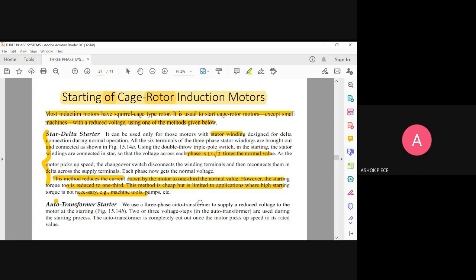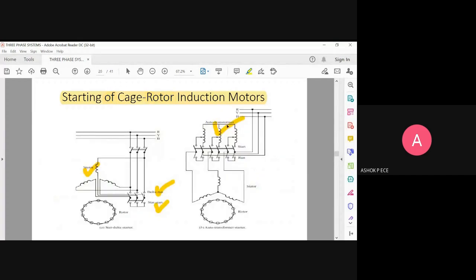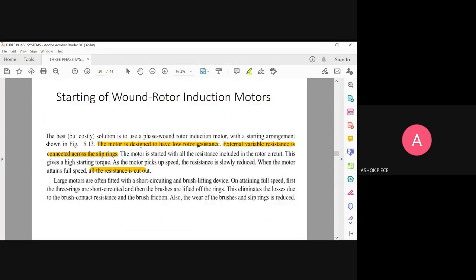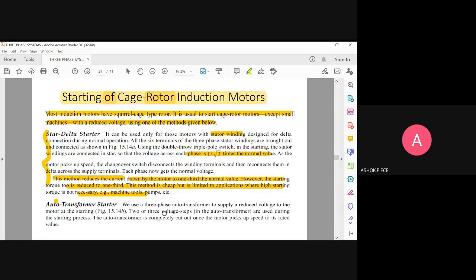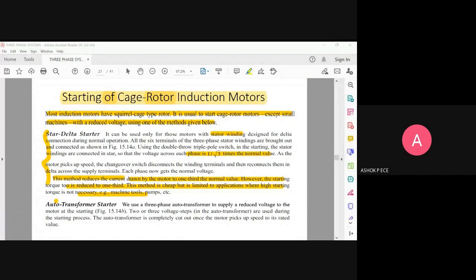The next one is the auto transformer starter. We use an auto transformer to supply a reduced voltage. In an auto transformer, the primary and secondary are in the same winding, and you have a pointer — the upper portion is primary, the lower portion is secondary. By moving this pointer, you can reduce the voltage. Initially while starting, the voltage will be very low. Once the motor is completely running, the auto transformer is cut out so the motor runs at full speed. These two types of starters are available for induction motors.